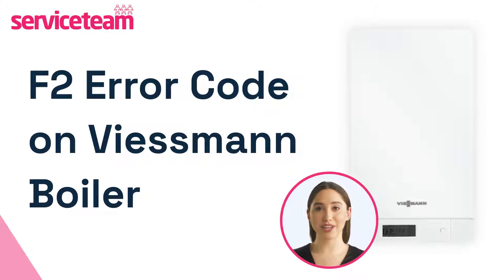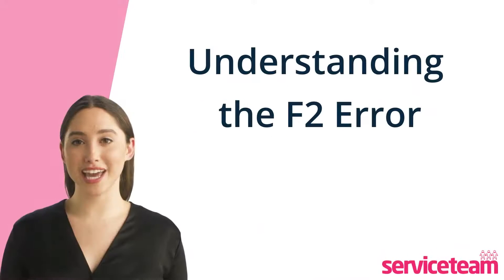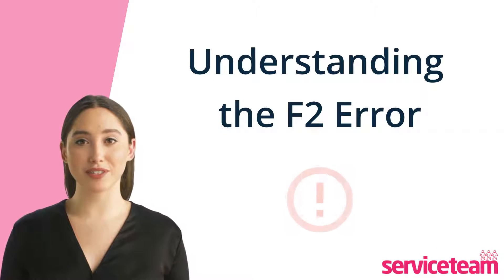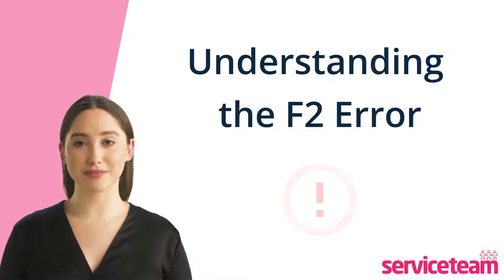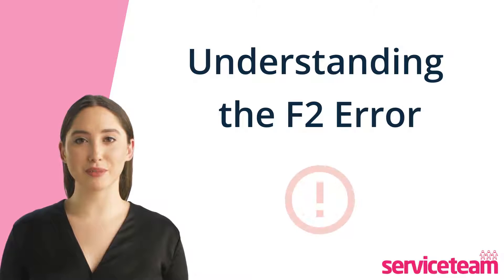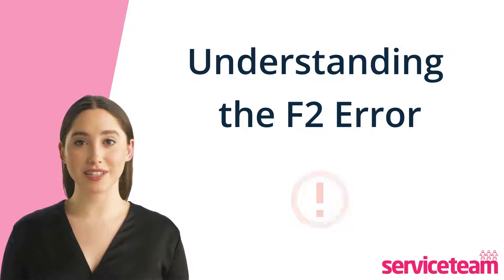Let's figure out how to resolve the F2 error code on the Viessmann boiler. The F2 fault code on a Viessmann boiler means your burner is locked out, so there's no flame to heat the water. This leads to a lack of central heating and hot water.